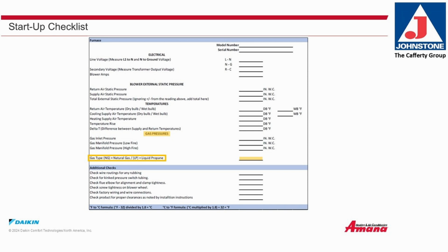Additional checks: check wire routing for rubbing, check for kinked pressure switch tubing, check flue elbow for alignment and clamp tightness, check screw tightness on the blower wheel, check factory wiring and wire connections, check the product for proper clearances as noted by installation instructions. And for your convenience, at the bottom of the page, we've included the formula for converting Fahrenheit to Celsius and Celsius to Fahrenheit.